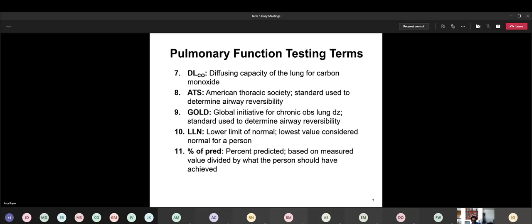You just keep it in your mouth, take in a deep breath, hold it, and then exhale back through the mouthpiece. What the analyzer, or the machine, is looking for is how much carbon monoxide came back in that breath when you exhaled it back out. If there's a diffusion problem, a lot more came back than should have. If there wasn't a diffusion problem, the machine should not be able to detect any carbon monoxide at all, or if anything, very, very low, because we know that hemoglobin much prefers binding carbon monoxide compared to O2. So there's nothing holding the gas back. Once you take the deep breath and hold it, it'll quickly diffuse over into the blood and connect with the hemoglobins.